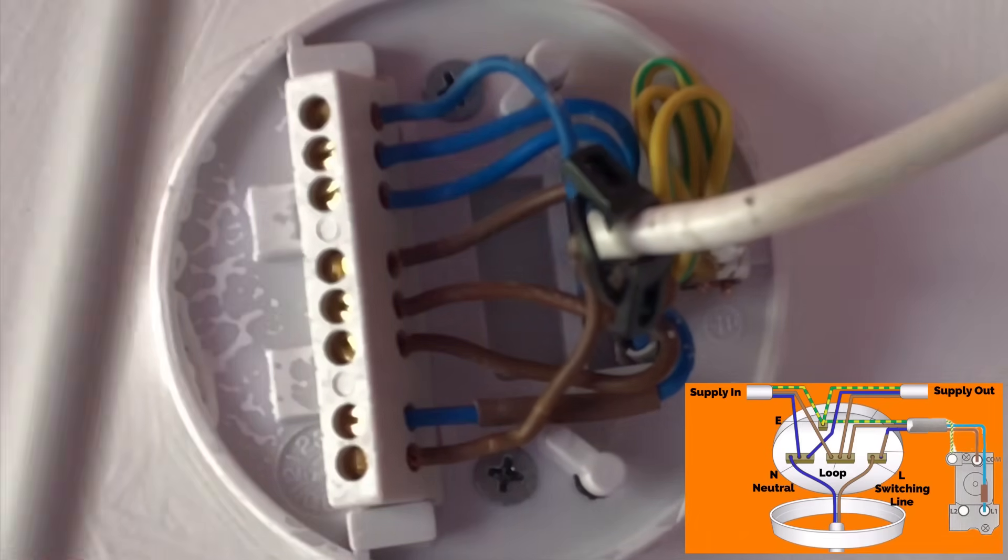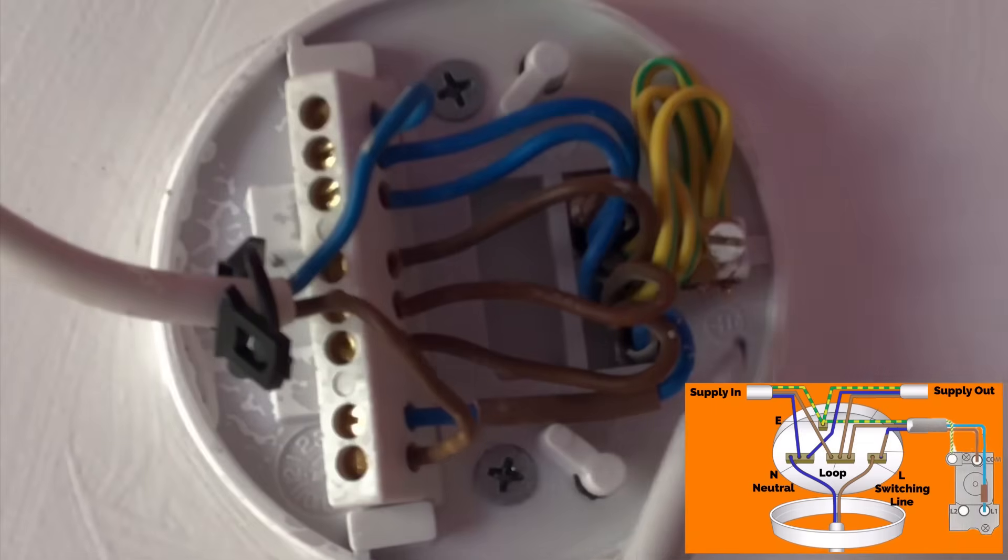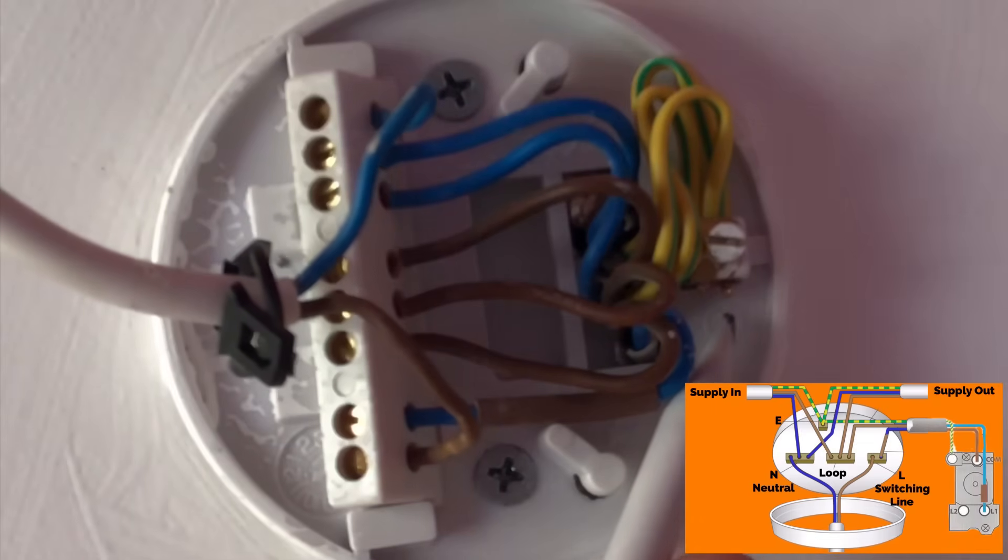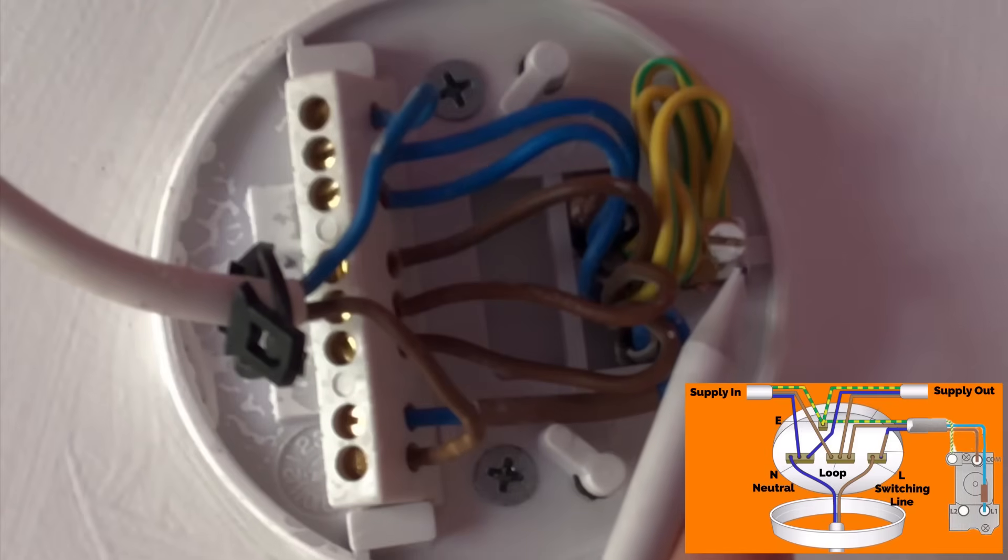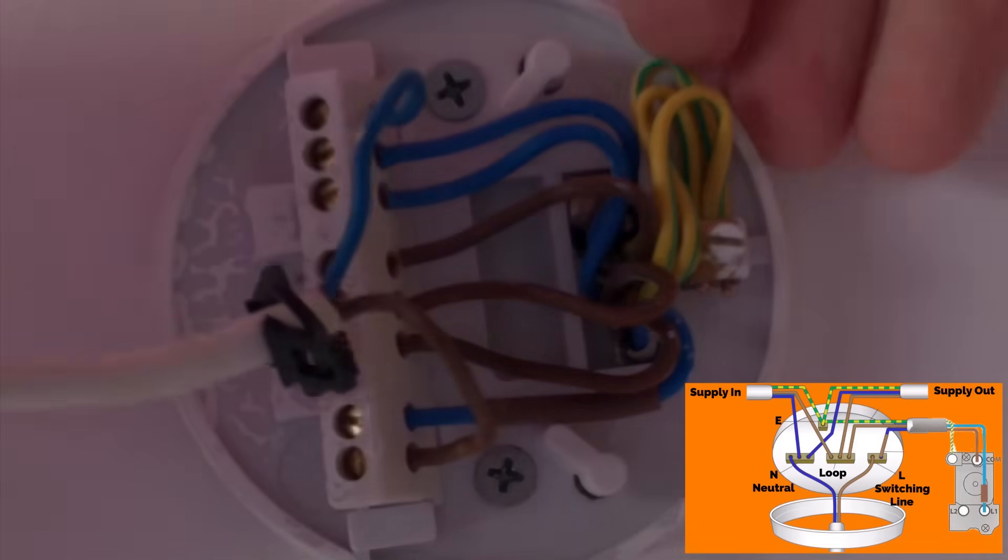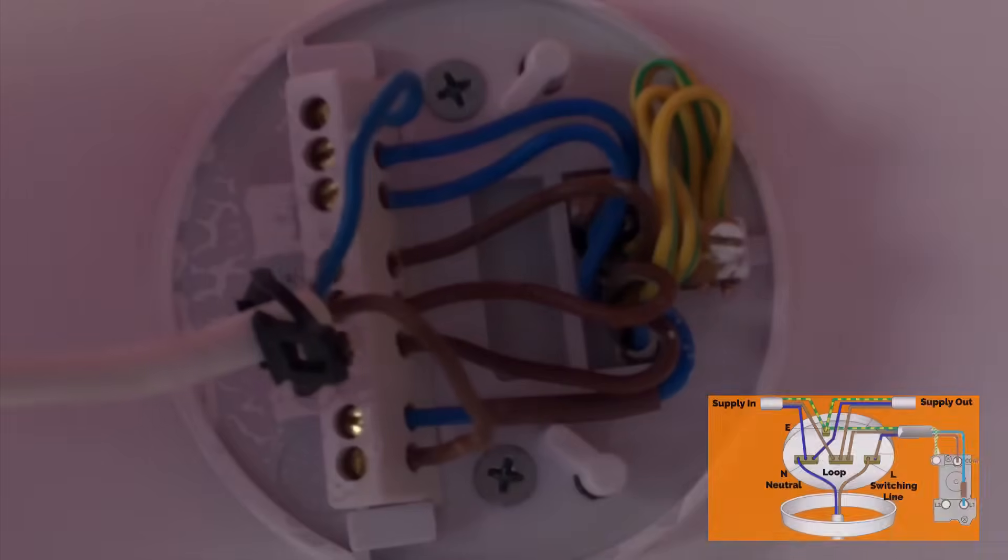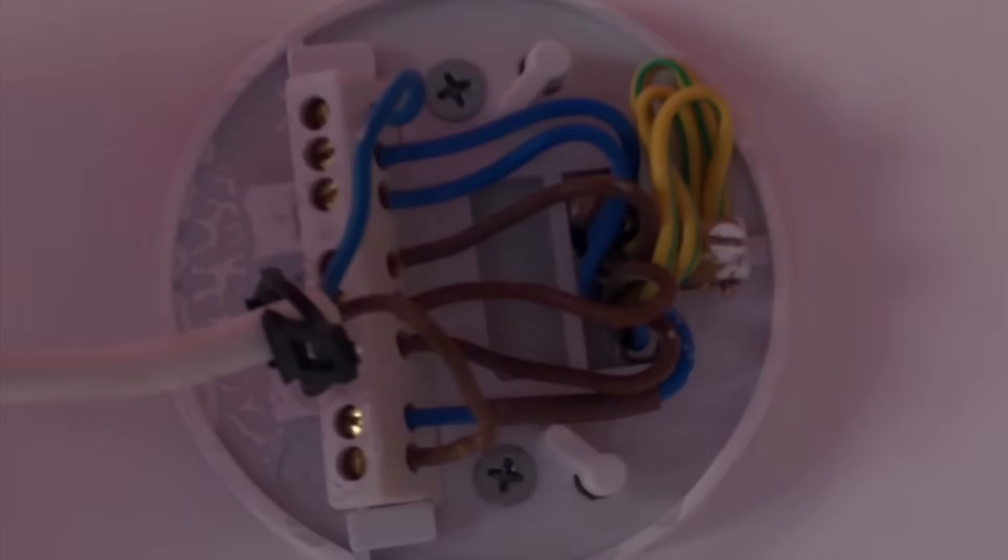The three CPCs, one from each of the twin and CPC cables, are connected in the earth terminal within the ceiling rose itself. The earth terminal is there in case the fitting is changed for one with an exposed conductive part, in which case the CPC would be needed. Let's have a look in another ceiling rose.